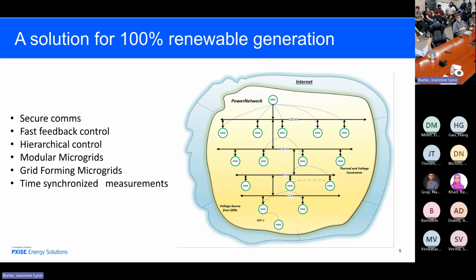Actually, in a microgrid system, we've seen 15-second delay in a traditional microgrid system, and that's due to the way the switches are located, the way the network is structured, the number of RTUs that are installed, number of PLCs that are installed that we have to get data from. So if there's a lot of extra devices in the network, you get added delay. And I can tell you, in a 60 hertz control system, I get 15 seconds of pure time delay. Why? Because of poor design of the communication infrastructure. We can overcome that problem.